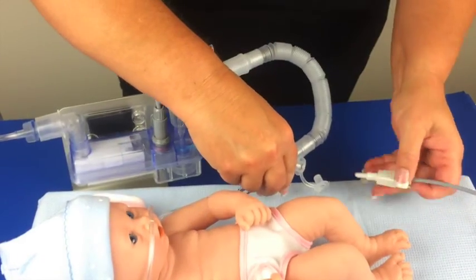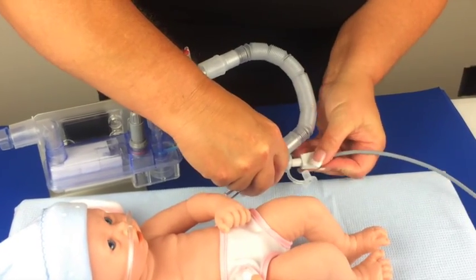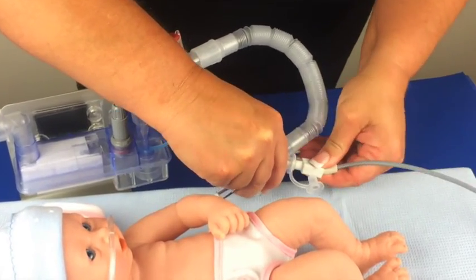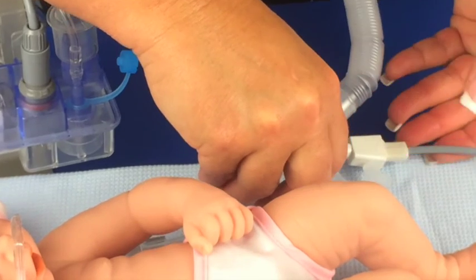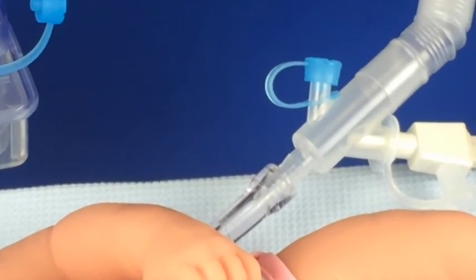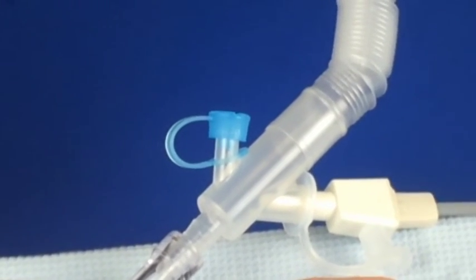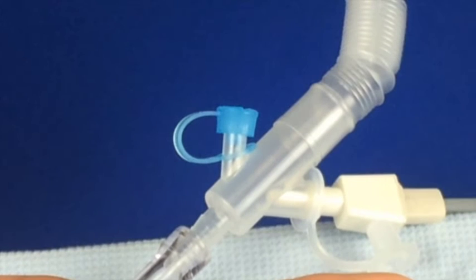Connect the temperature sensor probe to the temperature probe port. This is the white cable with white-tipped probe. Connect this probe to the temperature monitoring port of the circuit proximal to the nasal cannula connection. If nitric oxide sampling is required, attach the nitric oxide sample probe to the NO port with the blue cap, proximal to the nasal cannula connection.